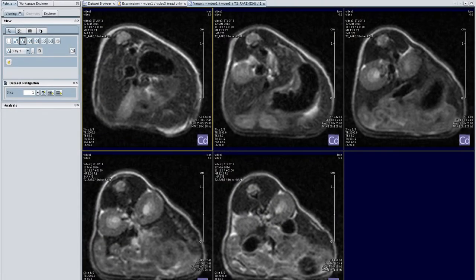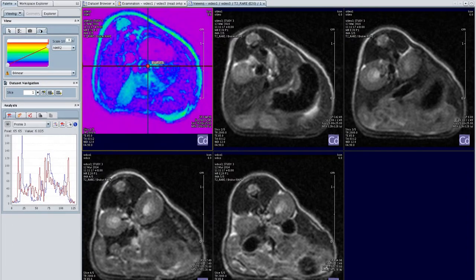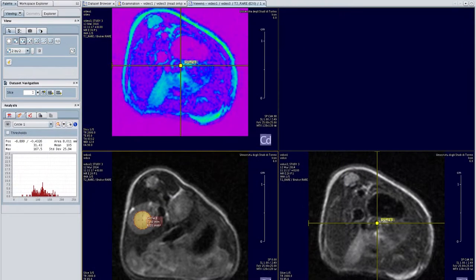In ParaVision software a new experiment can be started. Choose the part of the animal that you would like to scan, like head or abdomen. From the examination card, select the experiment you would like to run. The first one is the localizer, which is used to make reference images of the animal.